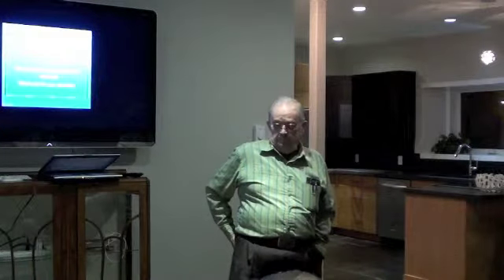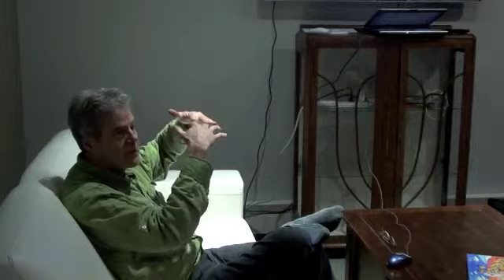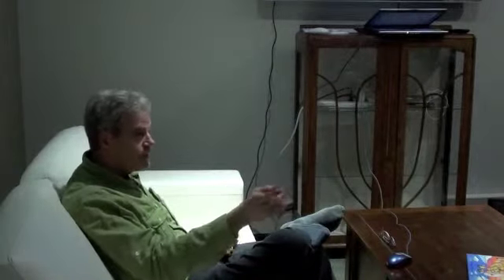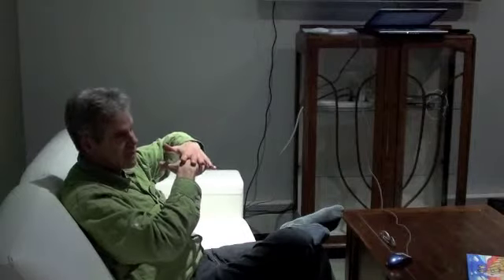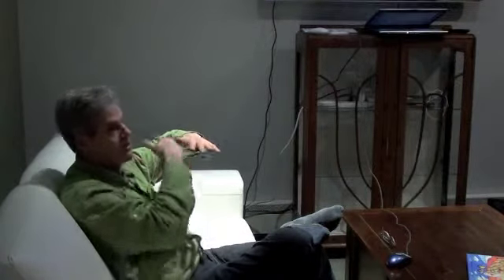So we figured a way, because it's a 2-story building and in the middle was another concrete floor. The ceiling of the lower floor and the floor of the one above was concrete. So we strapped pipe at a 6-inch spacing, which is a little closer than usual, to the metal pan under the middle concrete, and put the heating fluid through there. We were prepared for various backups, such as radiators in different locations. In some parts of the building we heated the walls because they were isolated from this radiant ceiling. So it's a radiant floor, radiant ceiling building, but because the pipes are underneath the concrete, they radiate downward a little bit faster than they radiate upward. So even though the downward heating job is harder, it balanced just beautifully.